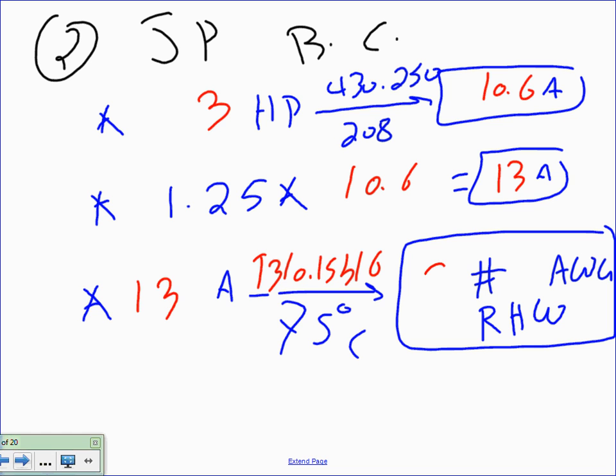So this will be 3 conductors, Chris, and can I get away with number 14? If you put number 14, I will mark you wrong, regardless of what the code says. We're designers. We don't put a single wire in a commercial building smaller than number 12. Why? Voltage drop. It's not worth pulling a stranded number 14 conductor for any load, especially 3 phase, or even single phase in a commercial or industrial building. Number 12. So our minimum when we go commercial or industrial is what? Number 12. Only in residential do we deal with number 14.